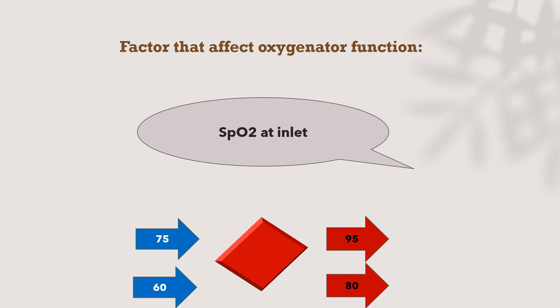The second factor is oxygen saturation at the inlet of the oxygenator. Using the same ECMO flow, same FiO2 from the ECMO side, and hemoglobin concentration of 12 g/dL in both cases: if the inlet saturation is 75%, the blood will come out at 95% at the rated flow. But if the inlet saturation is 60%, the blood coming out of the oxygenator will be 80%, and the patient will be hypoxic.